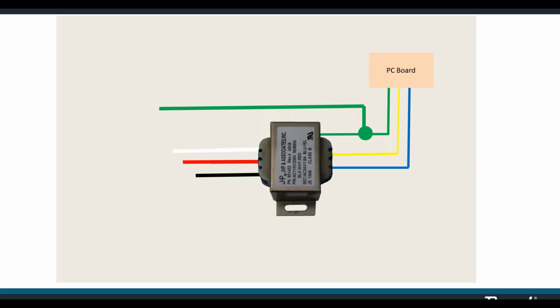There are 3 wires on the primary side of the transformer: white, red, and black. On the secondary side, that's the 24-volt side, there is a blue and a yellow. There's also a green ground wire that attaches to a ground screw on the cabinet. You're going to be wiring on the primary side only upon installation. The secondary side is already wired. Whether you're wiring 120 or 240, the ground is the same, so you might as well wire that up first.